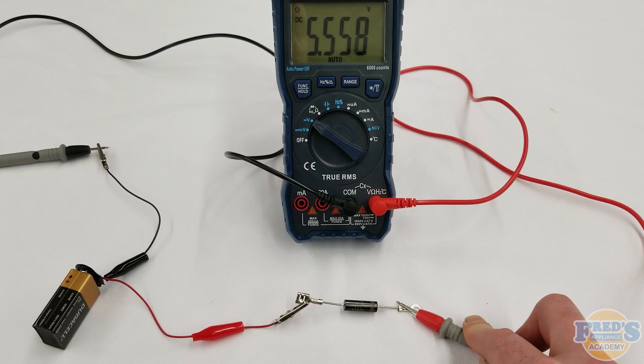Something you may not know is that your modern-day digital meter only outputs around 3 volts DC, which is not enough voltage to push through a microwave high-voltage diode. So how do we test them? Let me show you.